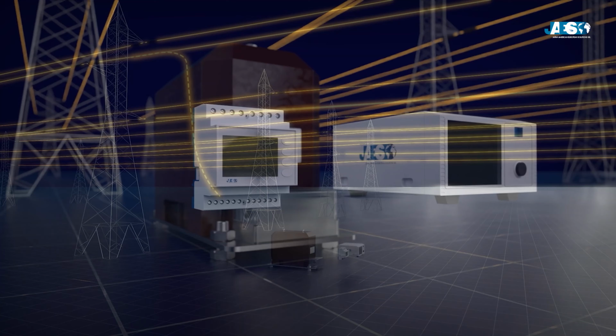When we talk about monitoring and controlling an electrical network, we are talking about systems that accurately measure currents and voltages at different points in the network. These measuring systems have a necessary component called a measuring transformer. A measuring transformer is an electrical device used to measure currents or voltages in a circuit without interrupting the main flow. Its primary function is to provide signals to measuring instruments or control devices without affecting the operation of the main circuit.